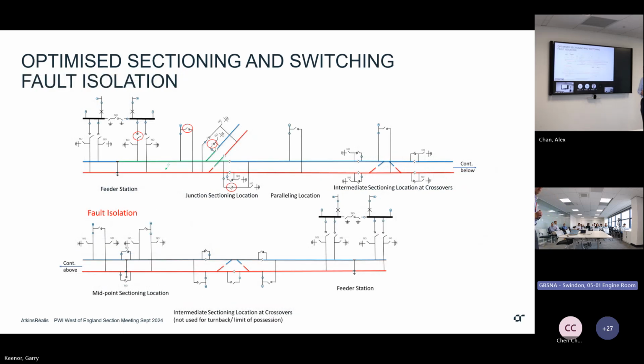We tested this layout by going through every combination of a single fault anywhere on the line. Can you feed around it? Can you reconfigure the equipment to maintain the railway around the fault while isolating it? We got all these red circles around the isolators that would need to change position to isolate that fault. With a fault on this section, four isolators would change position, you could then reclose the circuit breaker and recover the situation. We tested this, and the principle works through every subsection on that layout.